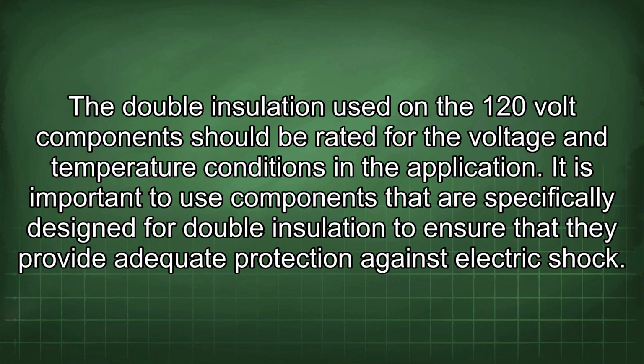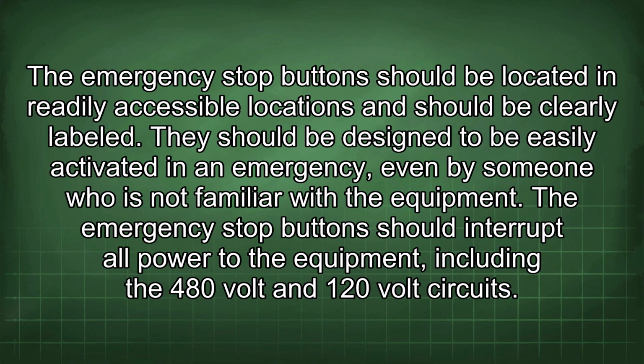The double insulation used on the 120 volt component should be rated for the voltage and temperature conditions in the application. It is important to use components that are specifically designed for double insulation to ensure that they provide adequate protection against electric shock. The emergency stop buttons should be located in readily accessible locations and should be clearly labeled. They should be designed to be easily activated in an emergency even by someone who is not familiar with the equipment. The emergency stop buttons should interrupt all power to the equipment, including the 480 volt and 120 volt circuits.